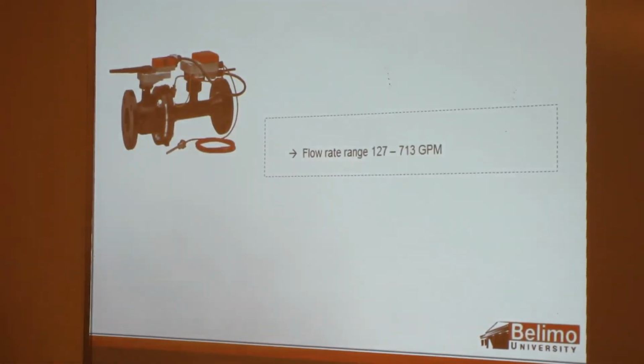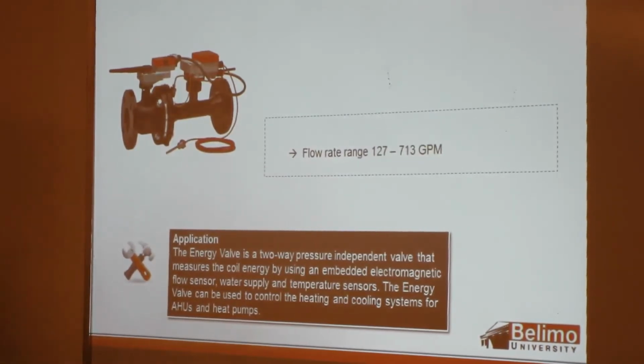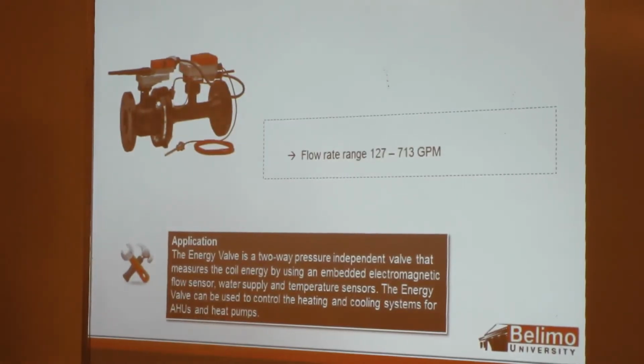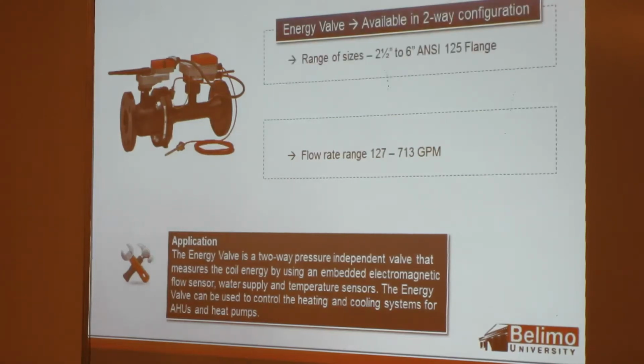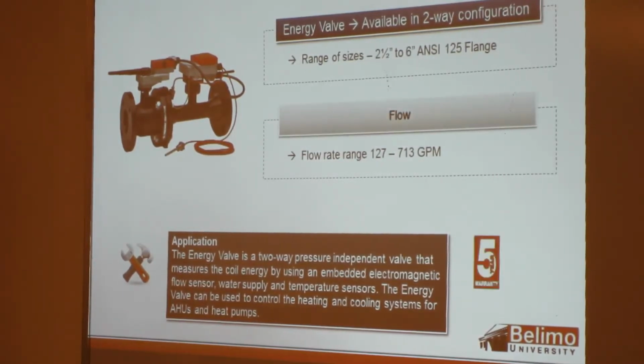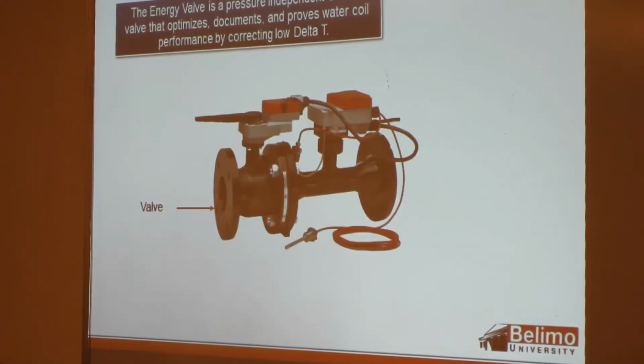The energy valve, as you can see, looks a lot like the EPIV. That's because it's based on the EPIV. We just put a couple additional features in there. It has the same flow ranges, everything. Same type of application, hot and chilled water. It can be used for air handling units, heat pumps, whatever the case may be. Available, again, only in 2-way configurations, ANSI 125 flanges. It's also got the 5-year warranty. Here's the description of what an energy valve is. It's a pressure-independent control valve that optimizes, documents, and proves water coil performance by correcting low delta T.